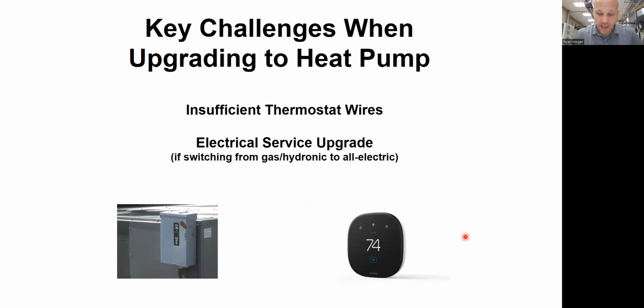All right, so let's say I have a DX cooling split system, or even a rooftop unit, and I've made the choice of replacing it with a heat pump. I'm going to do that. I'm pulling the trigger. I'm getting the heat pump for whatever reasons, either the economics, or they said they wanted to get rid of fossil fuels, whatever the reason. I'm going down the heat pump path. So, things that I might have to do other than just changing it out. If I'm going to change out my exact system for a brand new exact system, it's pretty easy, right? Turn the gas off, disconnect the electric, remove the rooftop unit, put the new one down. Maybe I do a curb adapter, maybe not, depends on the situation. Put it down, reconnect my stuff, I'm up and running, okay?